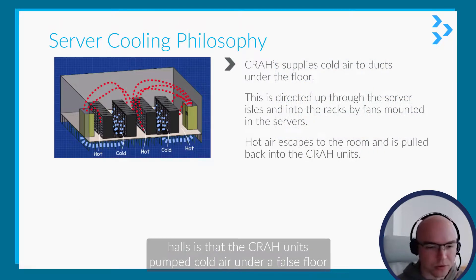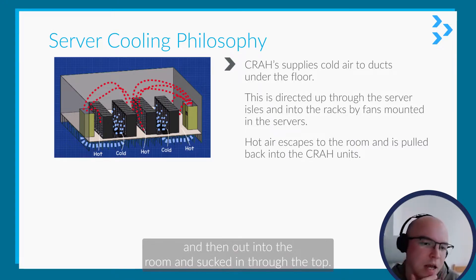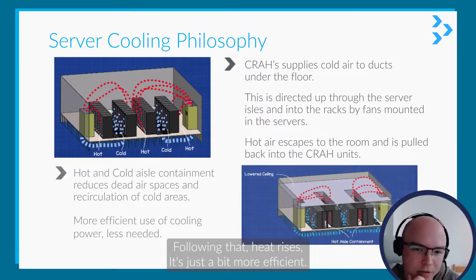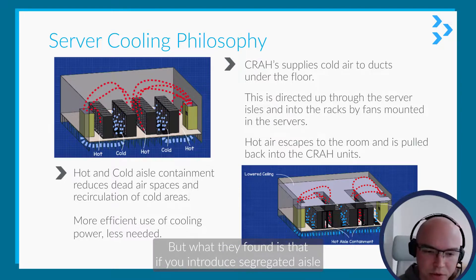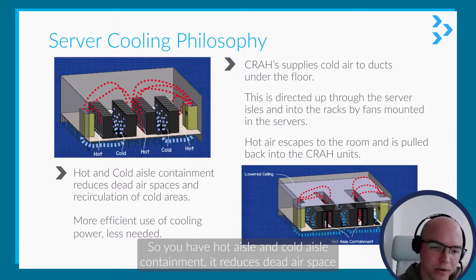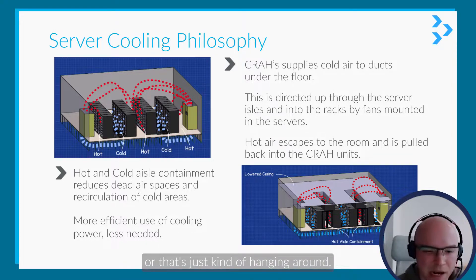The philosophy inside the halls is that CRAH units pump cold air under a false floor and bring it up through alternating aisles. This is then fed into the servers, out into the room, and sucked in through the top following the heat as it rises. What they found is that if you introduce segregated aisles — hot aisle and cold aisle containment — it reduces dead air space and prevents recirculation of air that hasn't gone through a server.